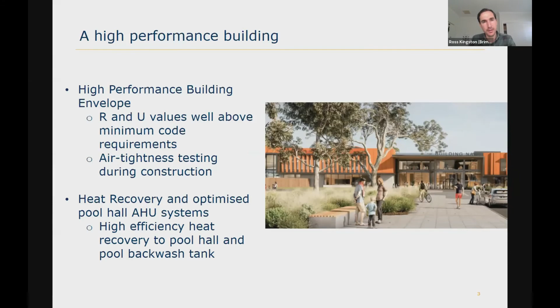This is just some design pictures which I thought I'd use to explain how our system's working in more detail. We've got what's called a 4-pipe heat pump system, a simultaneous heating and cooling system. It's an air-to-water heat pump, but its primary heat source for heating, when there's a cooling load, is the waste heat coming off the cooling load circuit. When heat demand surpasses what's available from the cooling side, it sources heat from the air, but that's just a quirk of the system we've got. It's a simultaneous heating and cooling system, and you can achieve some really high COPs, particularly when there's simultaneous heating and cooling demand.